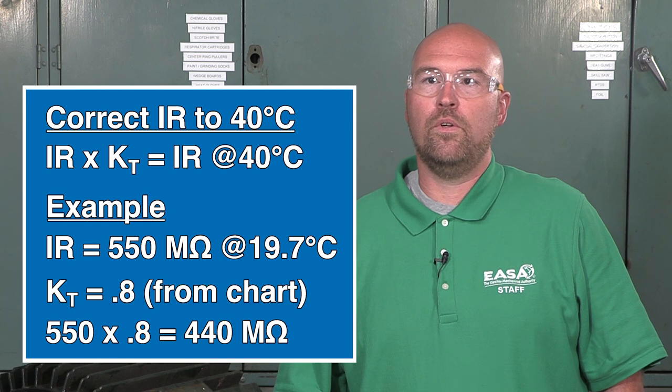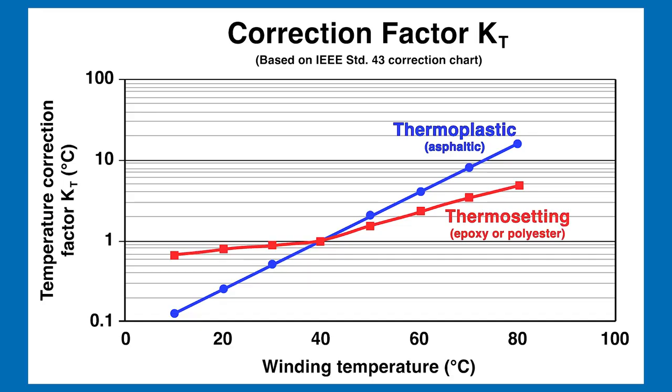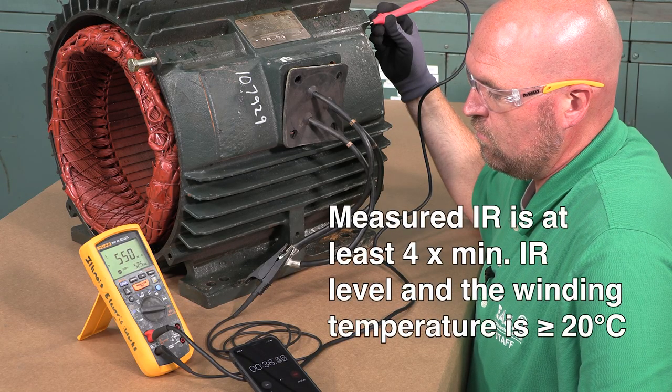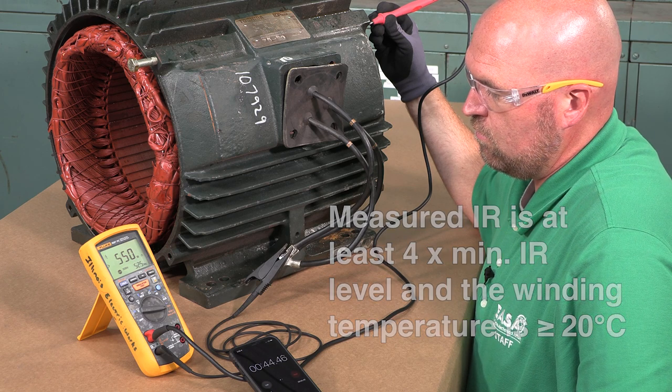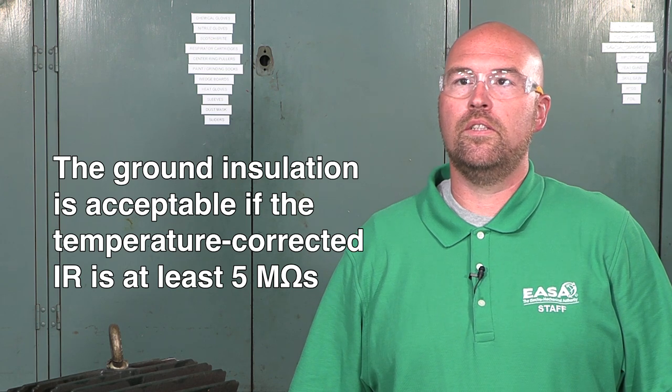To evaluate the IR test results, first correct the value to the standard 40°C per the ANSI/EASA AR100 standard, using the correction factor from the IEEE 43 chart. Note that all random windings have thermosetting insulation systems. Some digital instruments automatically correct the IR value to the standard temperature. If not, a good rule of thumb is that the measured IR value is at least four times the minimum IR level and the winding temperature is at least 20°C. Now compare the temperature-corrected IR test results with the minimum values at 40°C for a 460V winding in the AR100 standard, which in this case is five megaohms. The winding ground insulation is acceptable if the temperature-corrected IR is at least five megaohms.